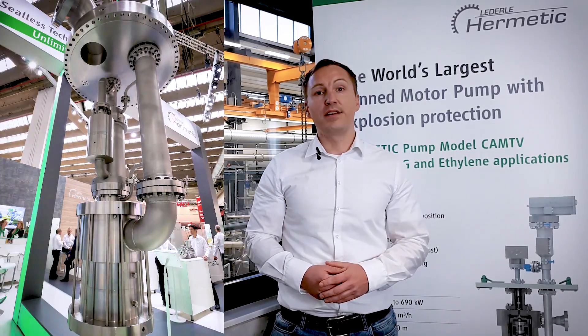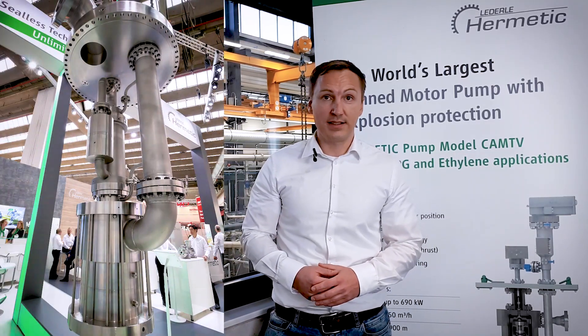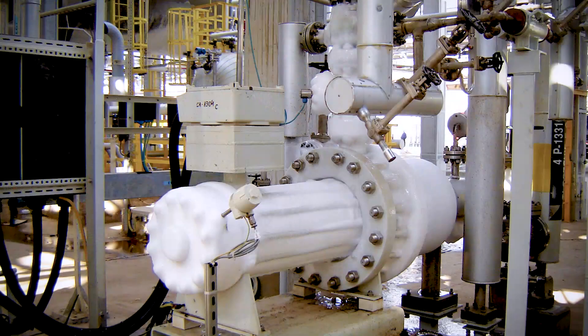As an example, on the next picture you see a pump that is used in a gas processing plant for nitrogen and methane. It is driven with 176 kilowatts at a temperature of minus 120 degrees, with an operating point of 190 meters head and a capacity of 900 cubic meters per hour.